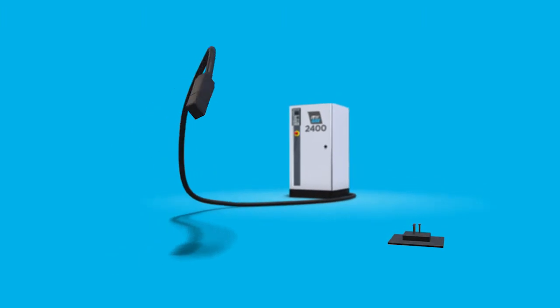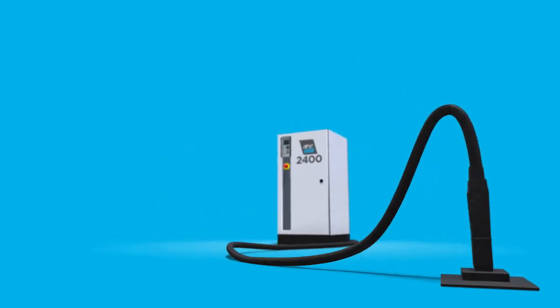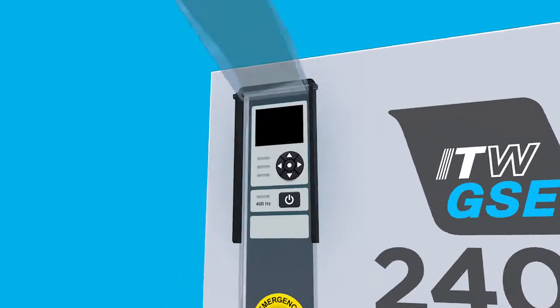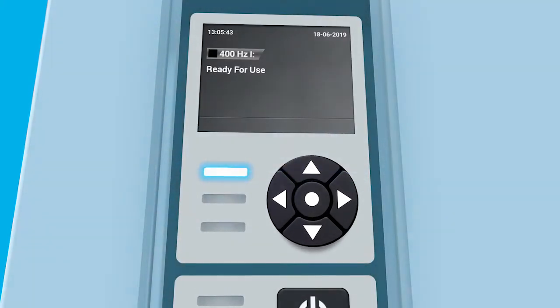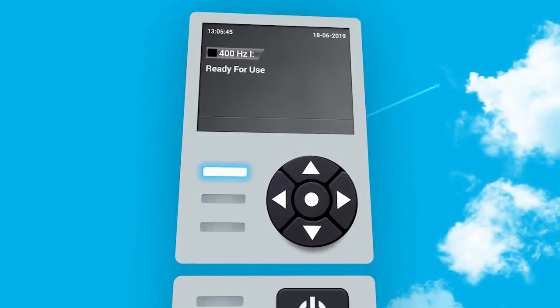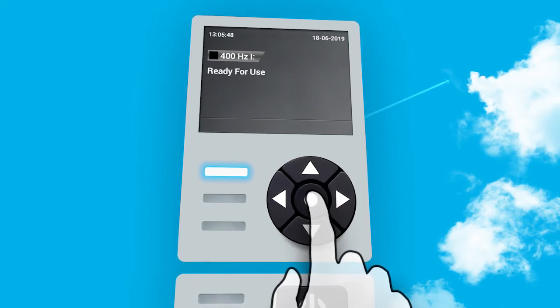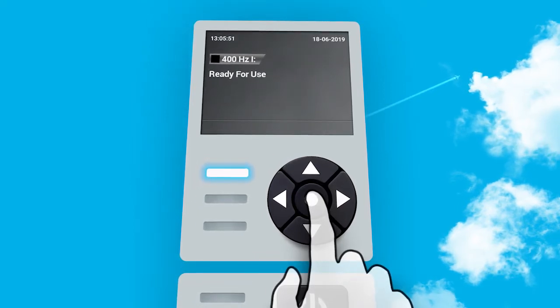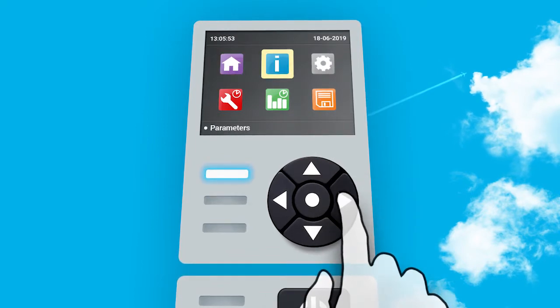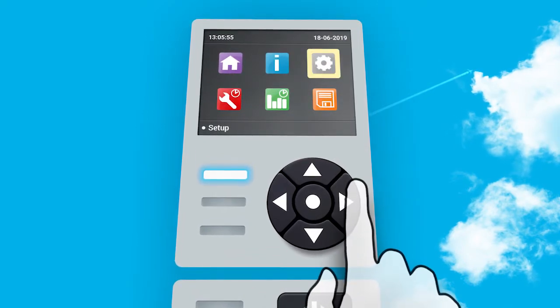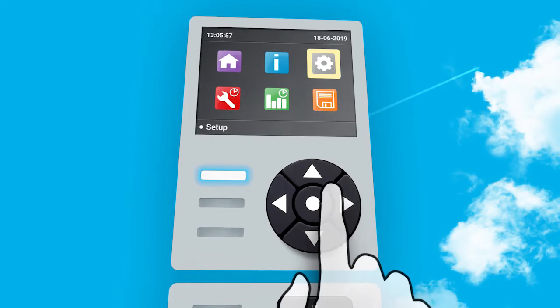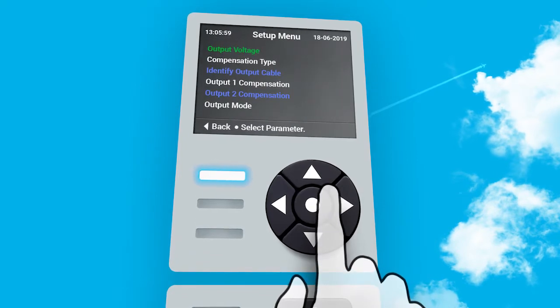Connect the ground power unit's output cable to the auto calibration plug. Turn on the ground power unit. Ready for use then appears in the display. To enter the setup menu, press the round button in the middle and hold it down for 5 seconds until the setup menu appears. Use arrows to highlight the setup menu. Press the center button to enter parameter list.